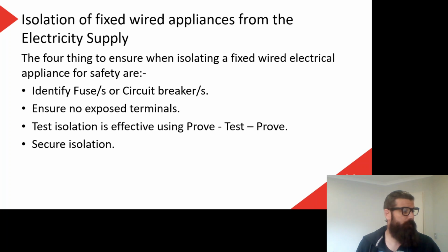Now I think we'll talk about prove, test, prove in a little bit. But briefly, that's checking that our meter works, testing the thing that I've isolated to prove that it's dead, and then testing that my meter works again. So proving my meter, test the circuit, prove the meter. And then we need to secure our isolation. So as I said before, that's generally with a lock. Physically lock that thing out so nobody can switch it back on.